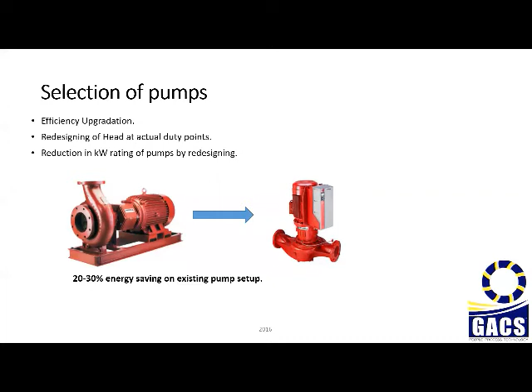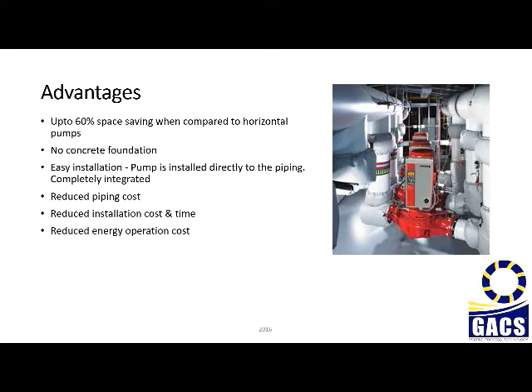Nowadays, the pumping technology has again upgraded, similar to the chiller, like the magnetic chiller upgradation. Similarly, here there are vertical inline pumps. So every OEM is nowadays providing this kind of technology. There are some advantages, like up to 60% space saving as compared to a horizontal pump. There is no need of a concrete foundation for installing this kind of pump. These pumps just hang in the in-out pipe of the header. It is very easy to install, and these can be directly integrated with the pumping system. It reduces the piping cost because it reduces the piping length also. There is a reduction in installation cost, and we can install it quickly. There is a reduction in time as well. These pumps are very efficient, meaning they will save a huge energy cost.